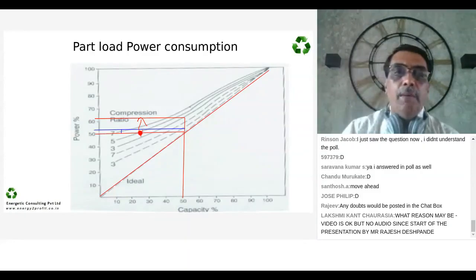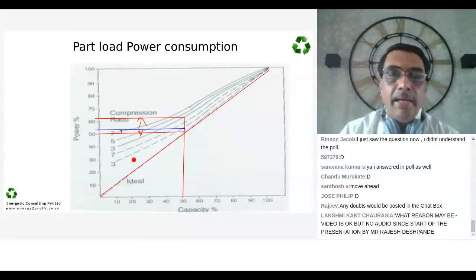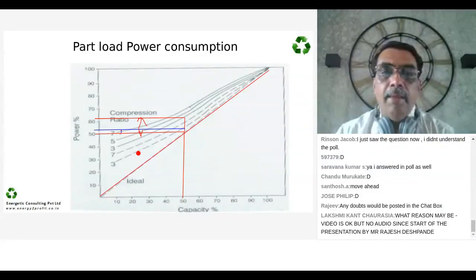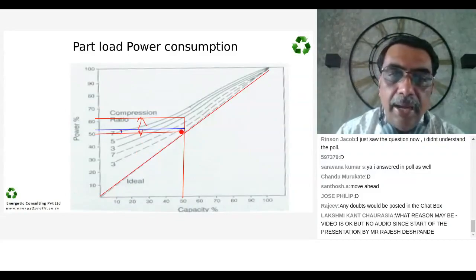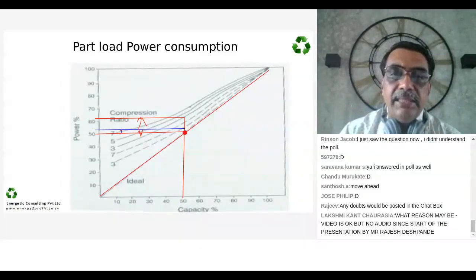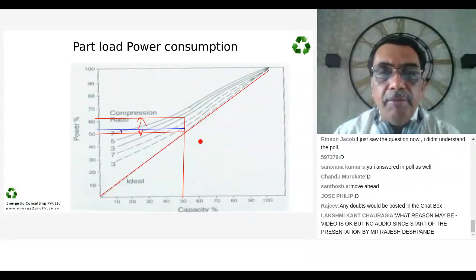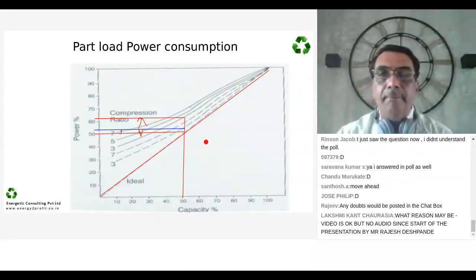This should have been my best efficiency point. This is where I am operating. This is my best efficiency. Guys, please note one more thing. If the pressure ratio is higher, the inefficiency is higher. Are you getting this point? If the pressure ratio is higher, the inefficiency is higher. Please note, very important issue.